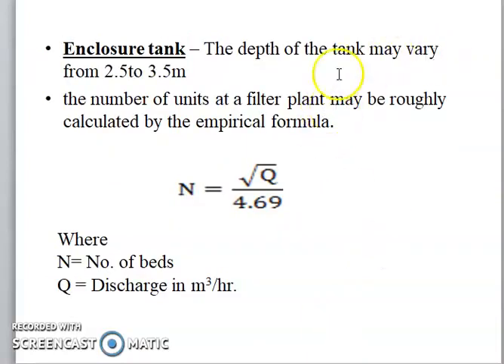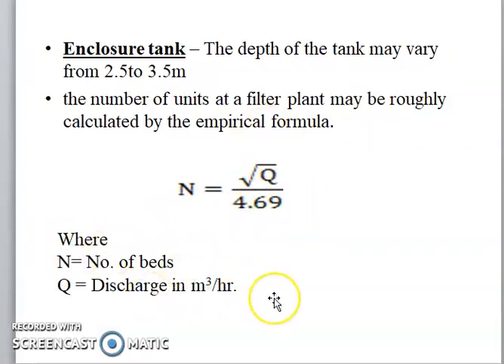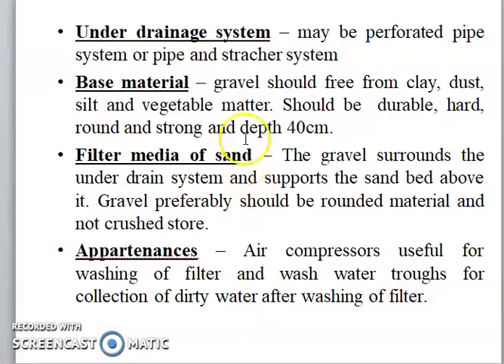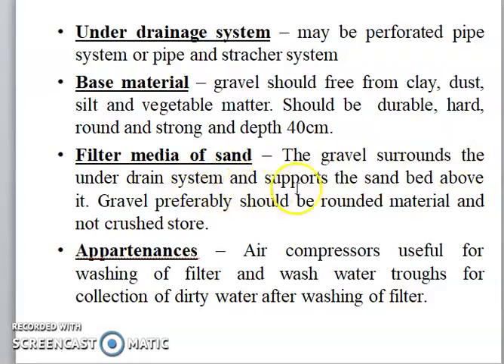The enclosure tank depth may vary from 2.5 to 3.5 meters. The number of filter plant units may be roughly calculated by the formula N = √Q / 4.69, where N is the number of beds and Q is the discharge in cubic meters per hour. The under-draining system may be a perforated pipe system or pipe and strainer system. Base material gravel should be free from clay, dust, and vegetable matter; should be durable, hard, round, and strong with a depth of 40 cm. The gravel surrounds the under-drain system and supports the sand bed above it; gravel should be rounded material, not crushed stone.